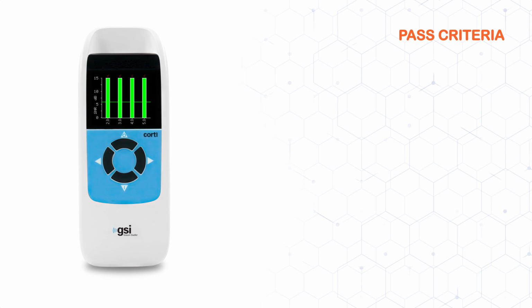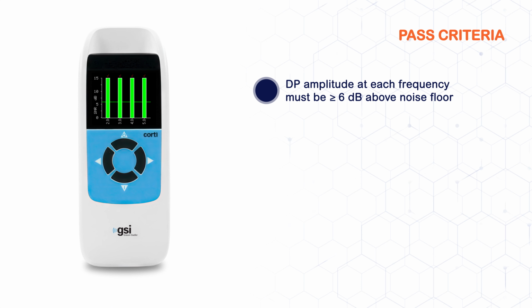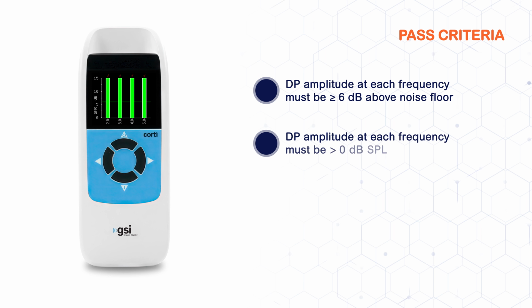There are two criteria for a pass outcome. First, the amplitude of the DPs at each of the 4 test frequencies must be at least 6 dB above the noise floor. In addition, the DP amplitude at each of the 4 test frequencies must be greater than 0 dB SPL. A pass or refer message will appear on the display screen of the Corti device when screening is complete. The device automatically stores the DPOAE screening results for each ear.